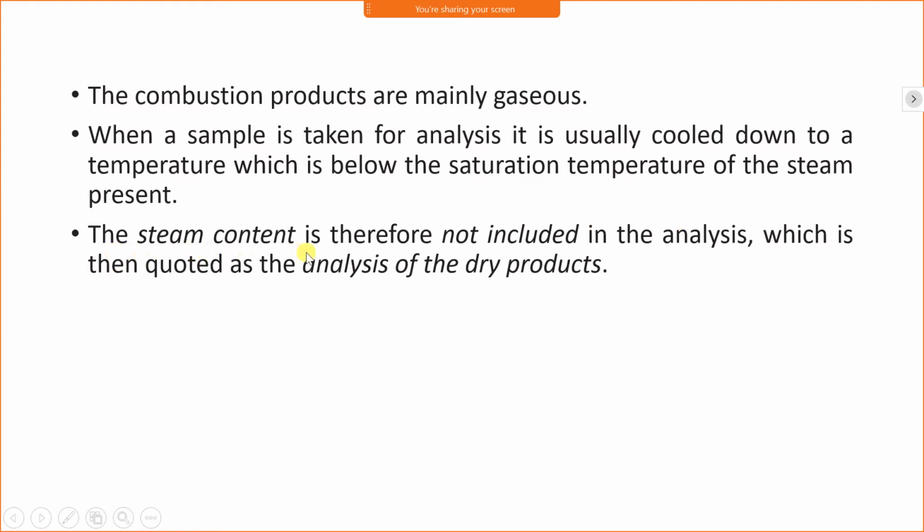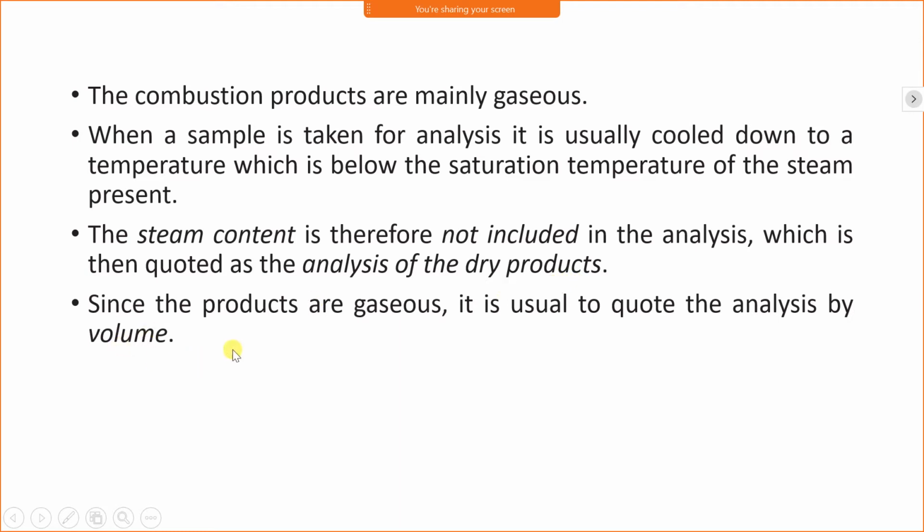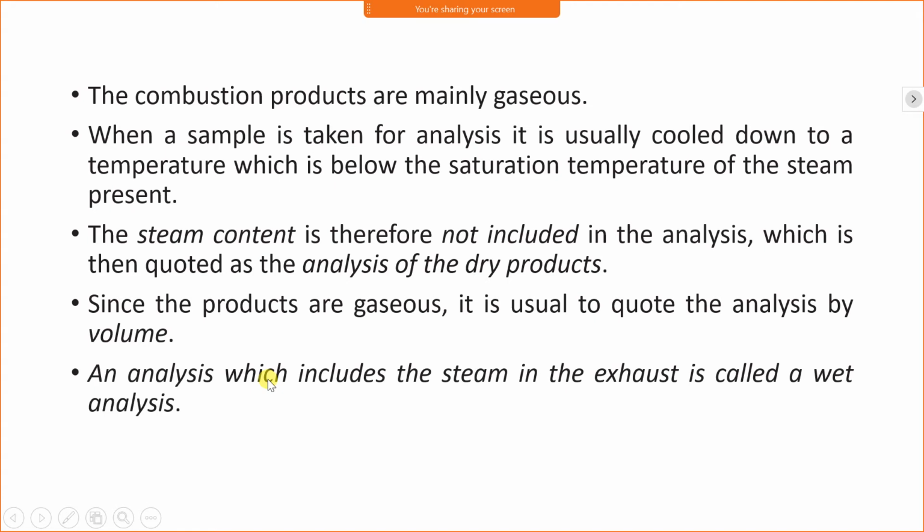The steam content is therefore not included in the analysis, which is then quoted as an analysis of the dry product. We condense the steam and do the analysis of the flue gas which is steam free. Therefore, this analysis is called an analysis of dry product. Since the products are gaseous, it is usual to quote the analysis by volume.